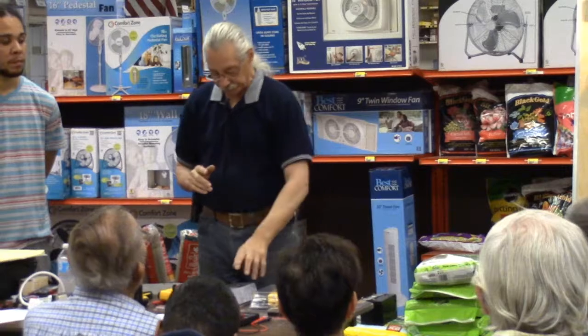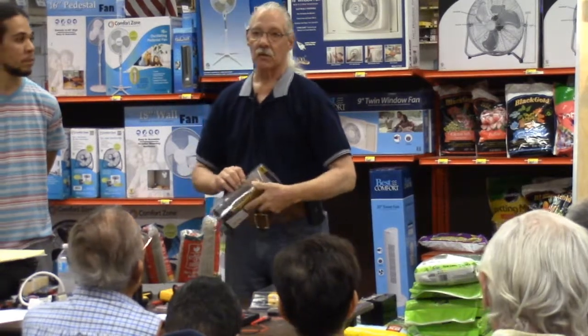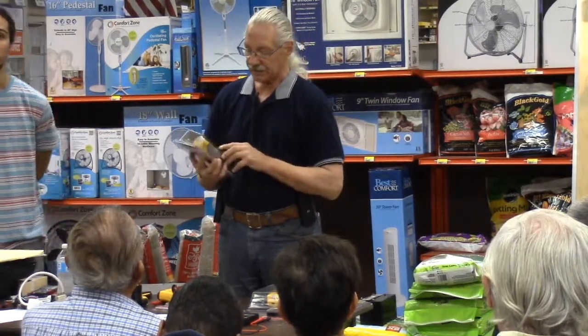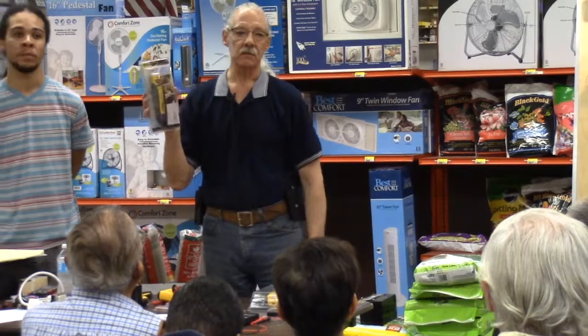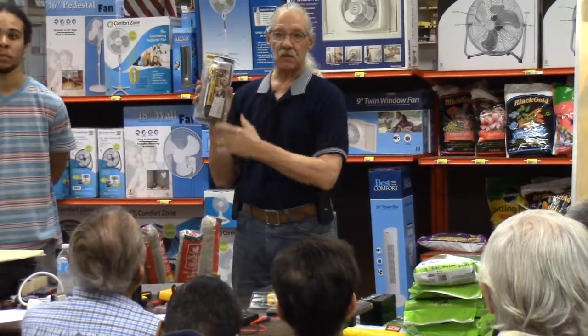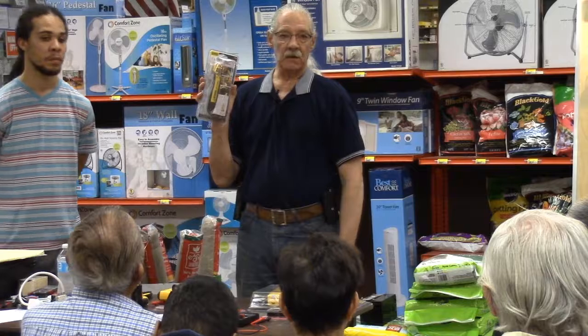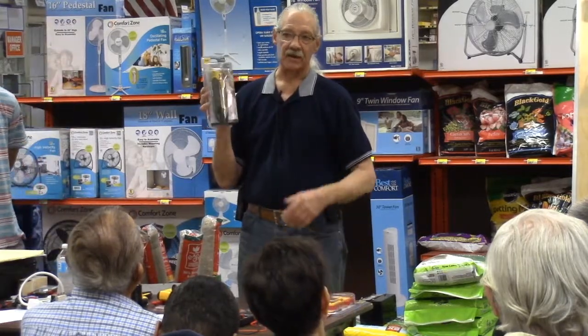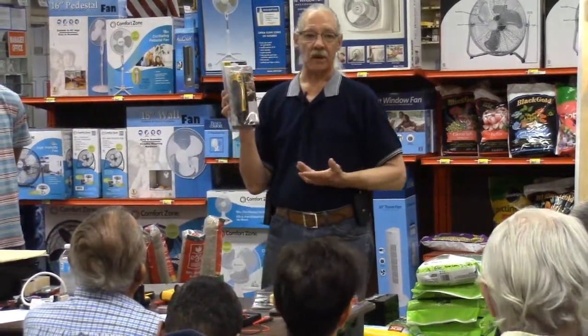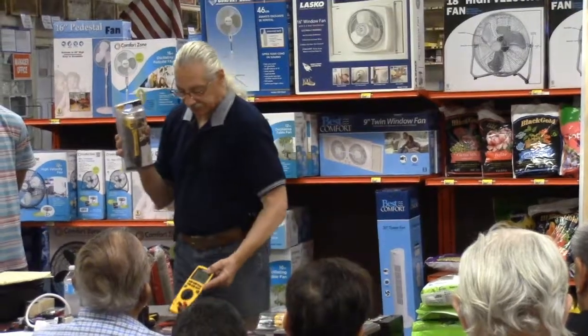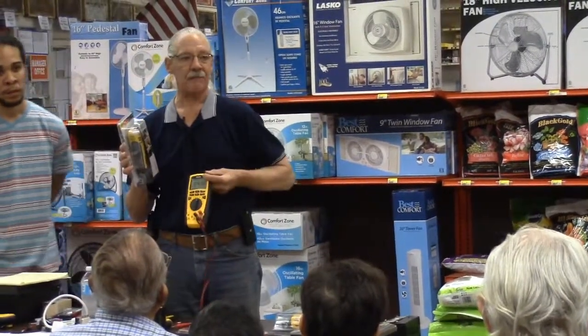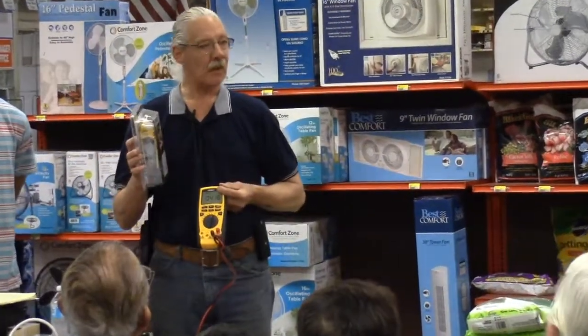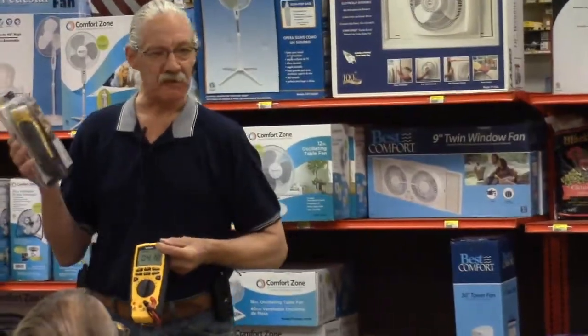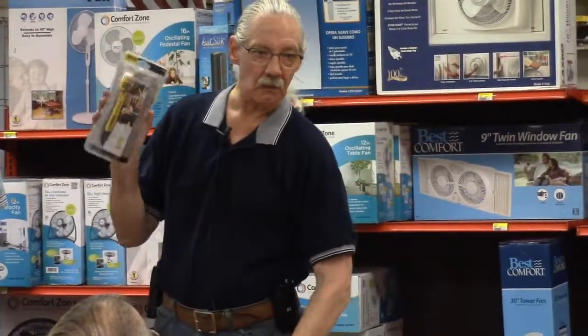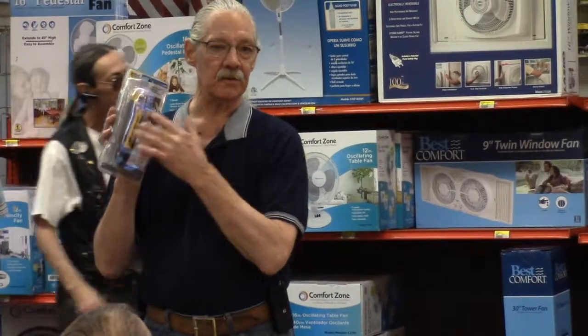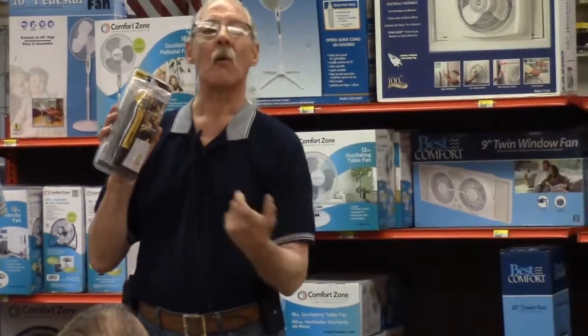When you're dealing with motors, the way to test that at the lowest level is a solenoid tester. Induced voltage is just that: it's from a very weak magnetic field, but a very sophisticated meter can pick it up. So now I'm going, well, why is there 50 volts in my dead circuit? The solenoid tester, that solenoid takes power to run.